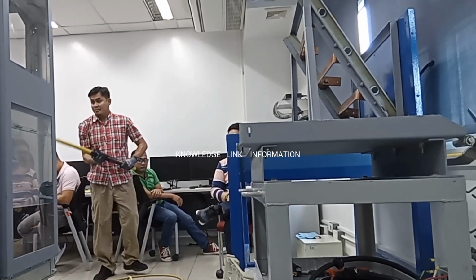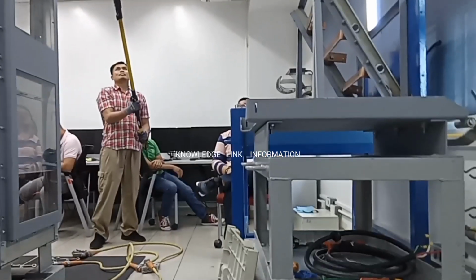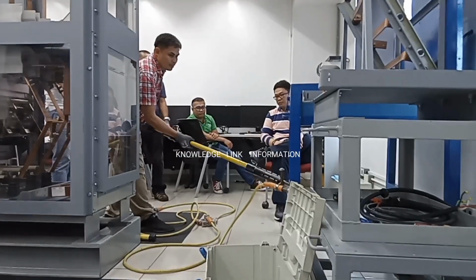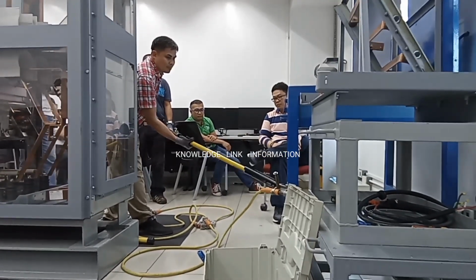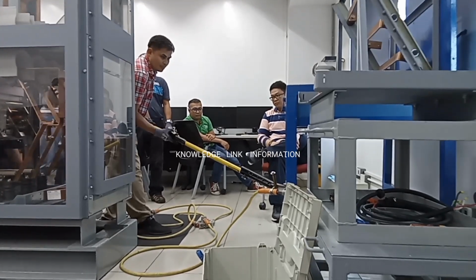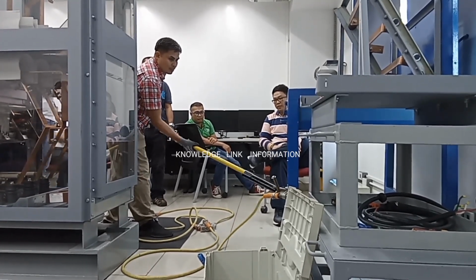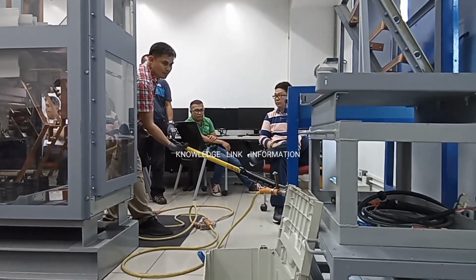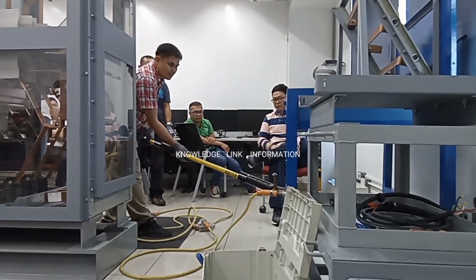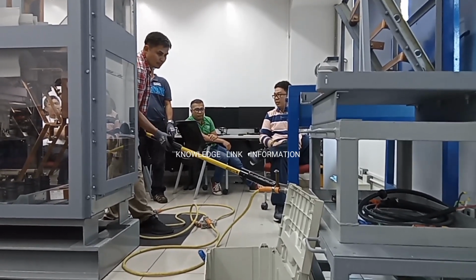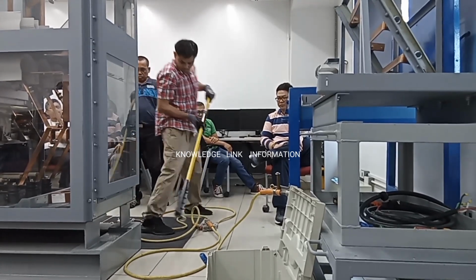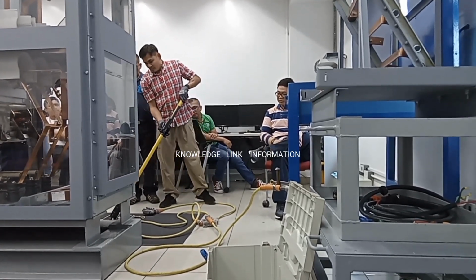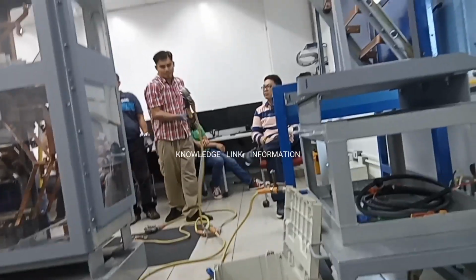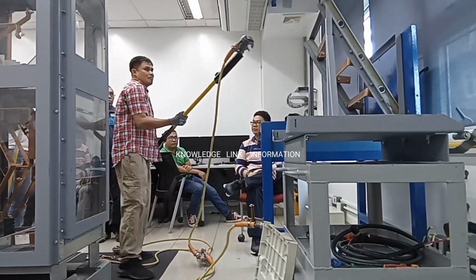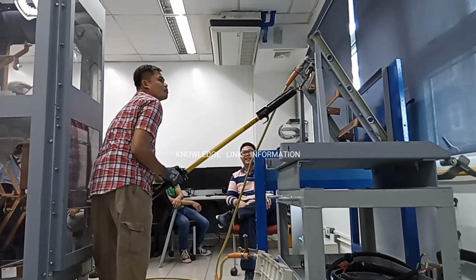Number 13. Pick up the telescopic shotgun stick and inspect whether it can operate properly without any defect. Number 14. Always connect first the common earthing connection clamp to any conductive ground surface. Be sure that all connection clamps are tight enough, in the horizontal direction of the cable lead, to avoid any damage. Number 15. Pick up the first phase connection clamp using a telescopic shotgun stick, and clamp it to the phase bus bar nearest to your body.